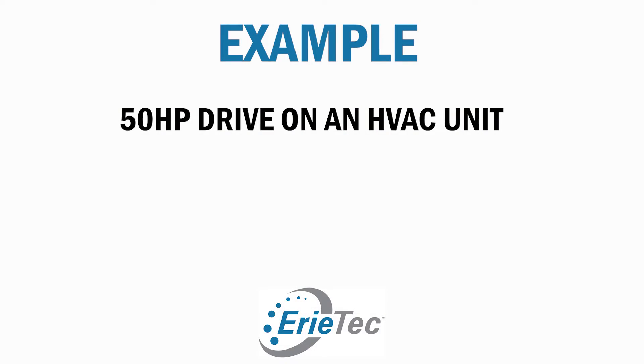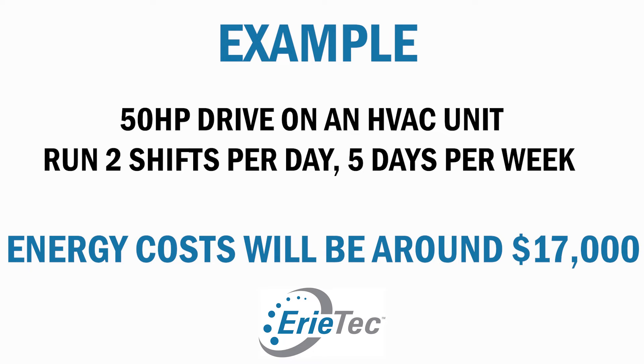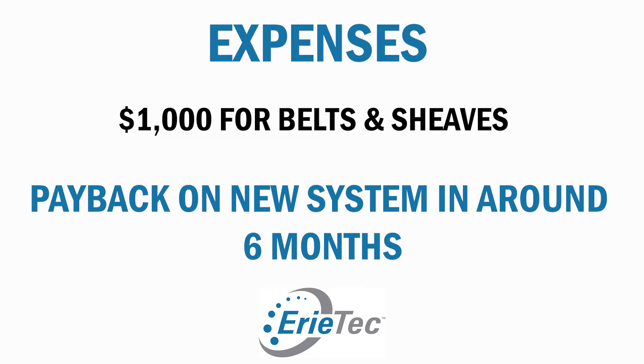So what do these efficiencies mean in dollars and cents? Let's take an example of a 50 horsepower drive on an HVAC unit that runs two shifts per day, five days per week. The energy cost will be approximately $17,000 a year. So how much of that $17,000 do you want to go up in smoke? The belts and sheaves for that 50 horsepower drive brand new cost a little over $1,000. Payback on a new system can be a little over six months. Do you want your belt drive to give you 93 to 94% of that work, or 83 to 84% of that work? It's vitally important to inspect your sheaves and tensioning on a regular basis.